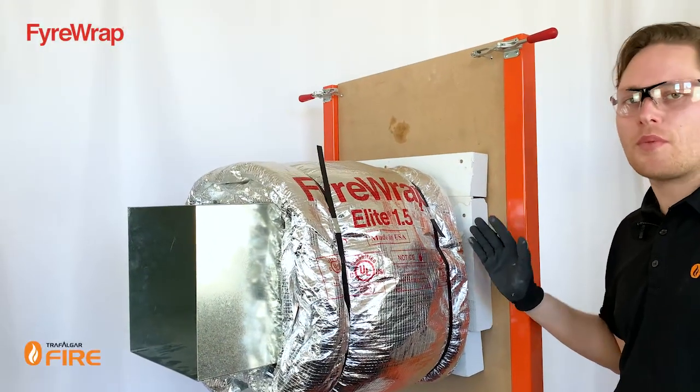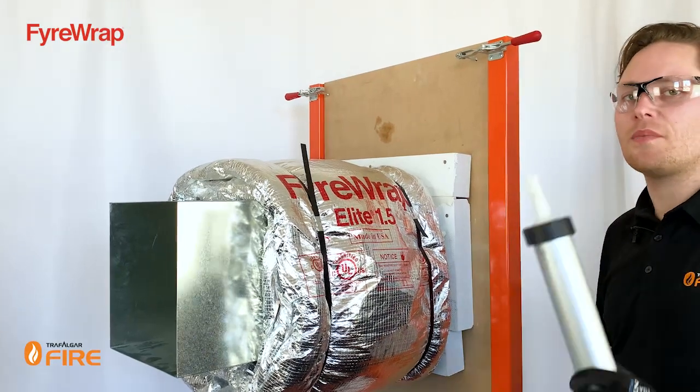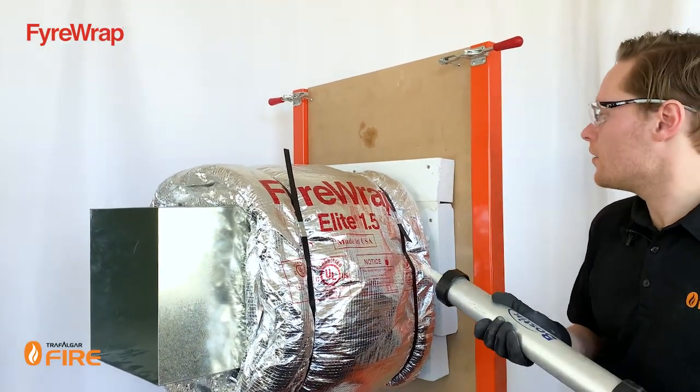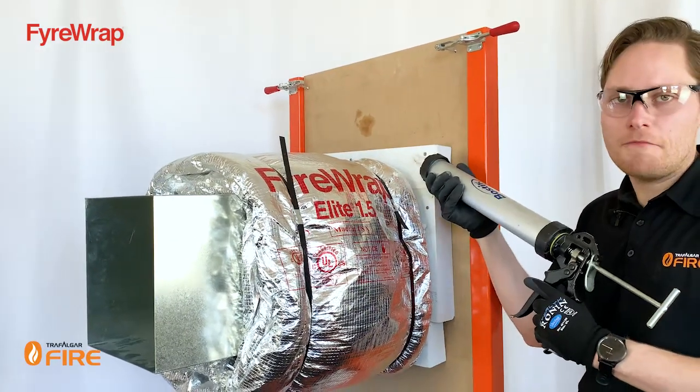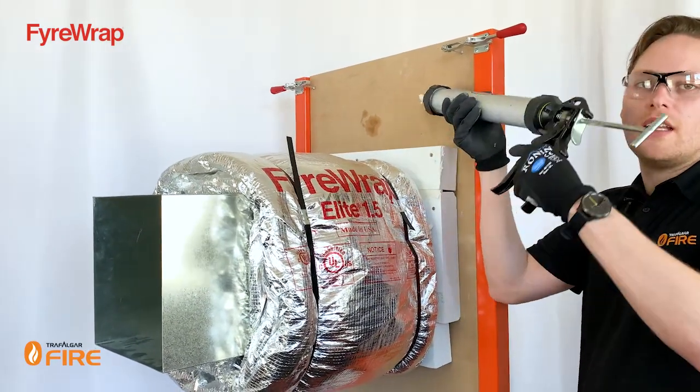Now that you've got your second layer of wrap away from the wall penetration, the final step is to seal it up with a bit of FyreFlex sealant. There are two key places to apply it: at the interface between the wrap and the MaxiLite, and at the interface between the wall and the MaxiLite.